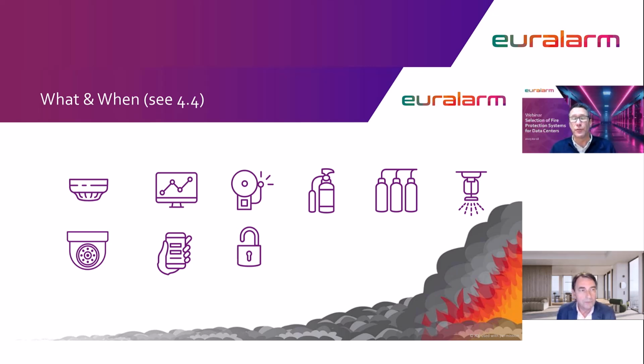So the two products I spoke of earlier, the one that reduces the oxygen takes about 3 times the footprint of the chemical additive, but it can flow a lot further. For big data centers with multiple areas, you can size a bank for the largest area and use a valve to send it to the appropriate room that needs it. In some cases, that footprint is critical and either not available or very expensive. In other cases, you may say, hey, I'm building a small modular reactor next door, this data center's in the middle of nowhere, I can do that.